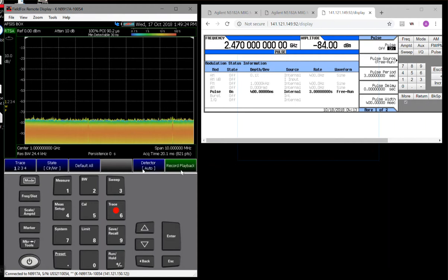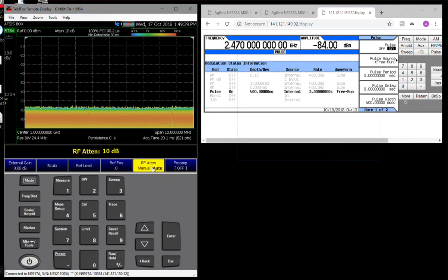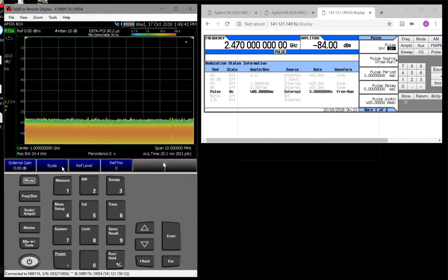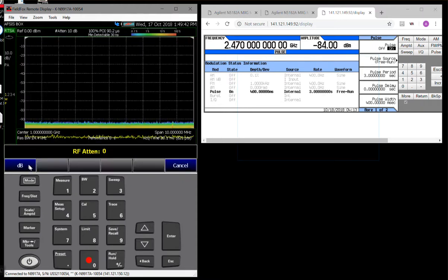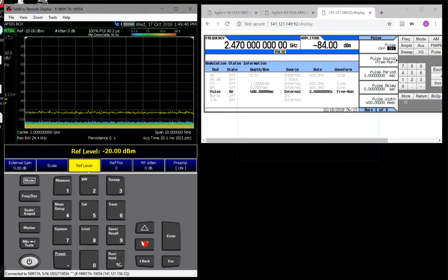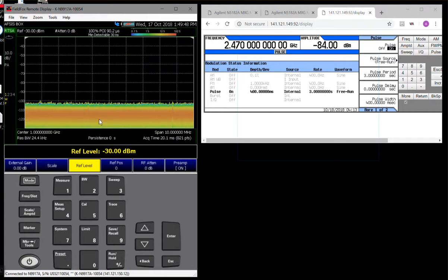So the way to really address the request of higher sensitivity is to implement frequency mask trigger in RTSA mode. So you're actually working on the frequency data, not the time data, so that it's actually a mask that would apply to this data.